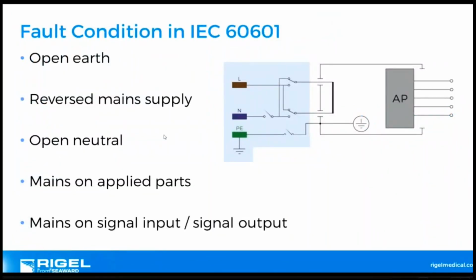What fault conditions do we have? Well, we have a number of different fault conditions. We can reverse live and neutral, we can open neutral, and we can open protective earth. And these are various fault conditions that are used within the 60601 standard. We also have mains on applied part, where we put the mains voltage on the applied part here, which is isolated. Then you have some SIP-SOP stuff again, but I'm not going to go into the SIP-SOP stuff because it's not part of general recurrent test.